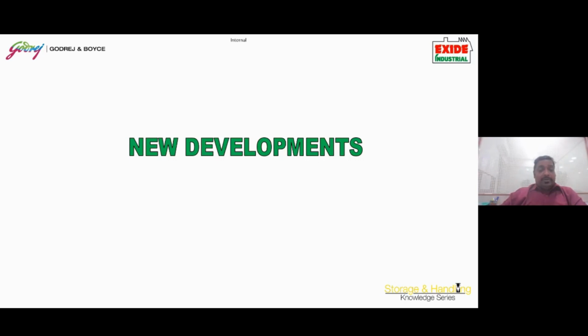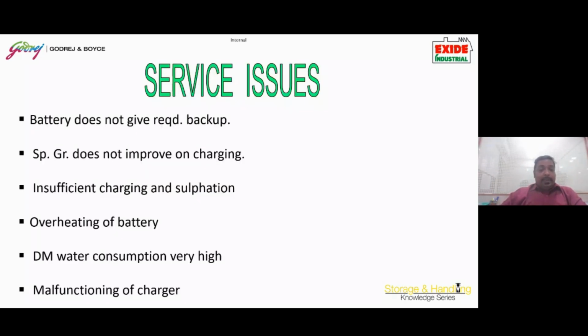So one by one, if I go back to these failure modes again, you as a customer must have also encountered all these failure modes. So if the battery does not give required backup, the probable causes are insufficient charging, a faulty charger, or one, two, or three cells inside the battery that have weakened and are not taking charge. Remember, 70 to 80% of backup issues can be solved at the site by proper charging, proper top up, and providing proper charging-discharging cycle, equalizing charging. If these activities are conducted in series as per the SOP, the battery can be revived on site.